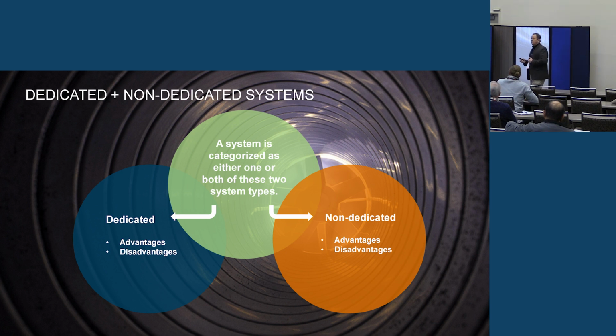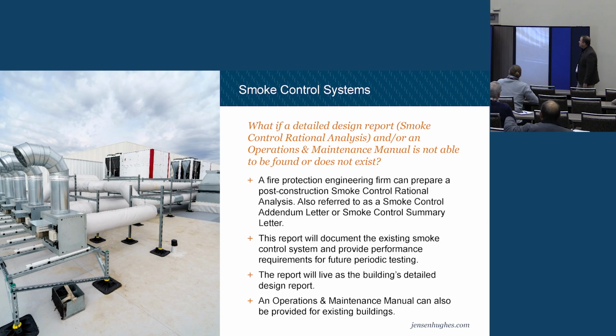Dedicated systems, the sequence of operations is probably going to stay, but in the same respect, it's also not getting exercised. So I've definitely learned in my career there are two systems that get more attention than any life safety system, bar none. Internet, and is the building warm or cool enough, right? So those two are the highest priority to the tenants. Unless there's an emergency, then they care more. But unfortunately, that's the reality. So dedicated systems tend to get forgotten about. So the maintenance may not be there. Testing a dedicated system can be challenging. If it's stairwell pressurization, I have to have all the doors closed because that's what I'm measuring my differential pressure against. So that's almost guaranteed off hours.